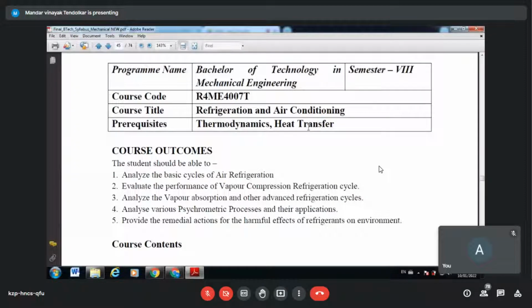Now, vapor absorption is a substitute for vapor compression, because the compression process naturally requires electrical energy. With vapor absorption, I can get rid of this compressor work. There is no compression, it's a simple absorption process. So I can basically claim to increase the COP.